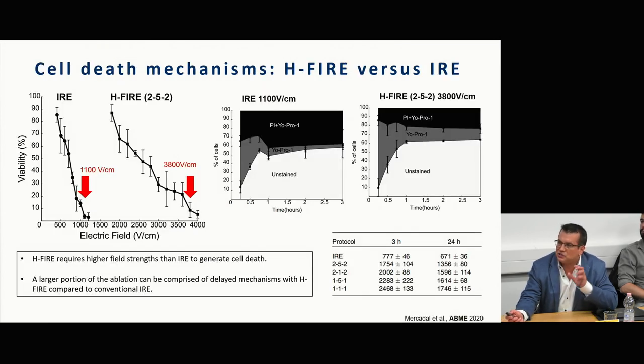Here's an initial study. I have other studies people can look at for reference later, but I'll highlight this one quickly: for a traditional monophasic IRE pulse, it might take 1,100 volts per centimeter to kill those cells. For an H-fire pulse, or biphasic pulse field ablation type pulse, using the same energy delivered, you're going to need more than three times that field, so 3,800 volts per centimeter.